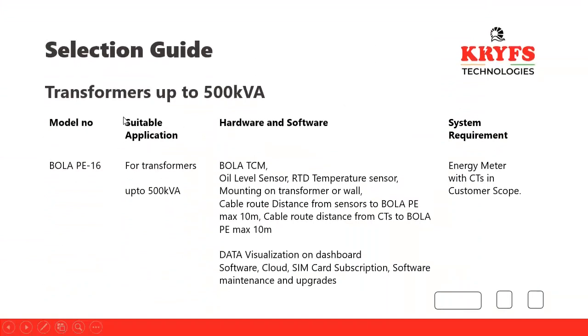So the model offered for transformers up to 500 kVA is BOLA PE-16, which will include oil level sensor, temperature sensor and some accessories. Okay. Data visualization, software, etc. comes along with the product. If on site, there should be energy meter already with CTs already installed. If it is not installed, then we can provide the energy meter and CTs at an additional cost. Or we can skip that monitoring also if we want.